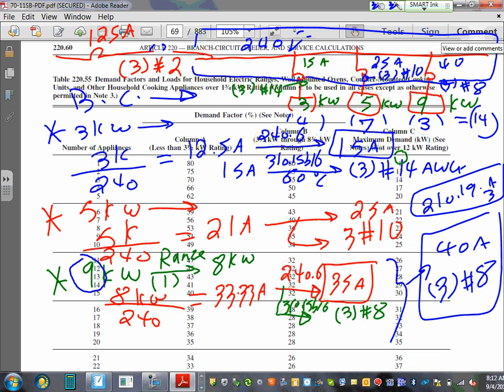Any comments, guys? Any questions? So what we did, now I have 14 circuit breakers in this panel. I sized them. 14 circuit breakers, and a main, and a feeder, and a branch circuit. Now, pick your tools, Adam, and get your conduits and start pulling wires, right? That's what we do as designers. Our job is to size all these branch circuits, feeders, and service. We're not just doing math for the sake of math. We do the math to size equipment. The electricians depend on us to put something on a blueprint for them to go install it. They will depend on you.